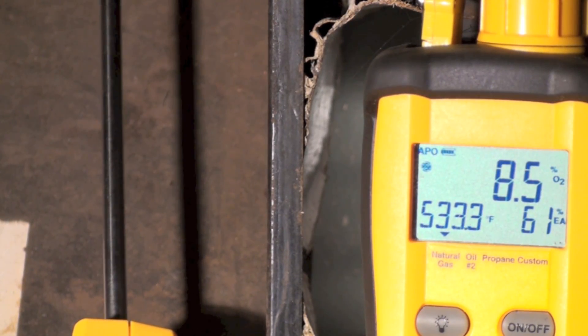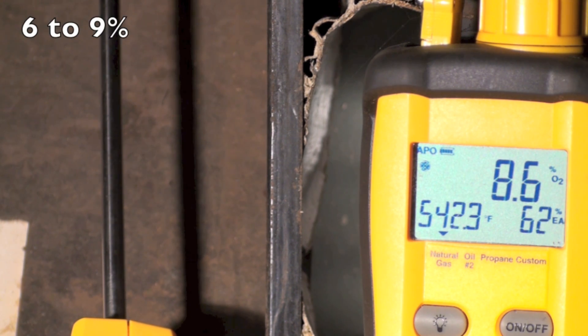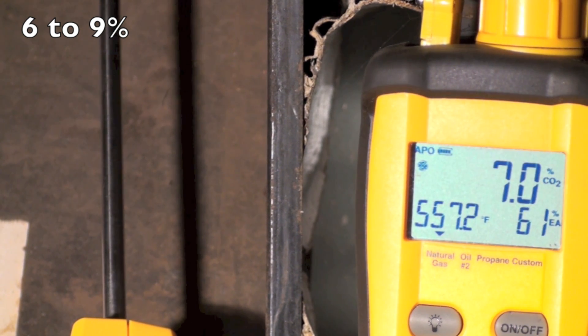Okay, here we are pretty much settled down in the burner that has very little combustion air, the lowest amount we can get away with. Now, our O2 is 8.7, our CO2 is 7.